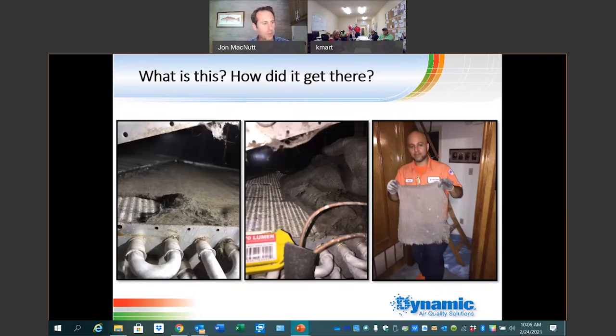But there are quotes where we can talk about the coil and say, not only is that affecting the performance or the efficiency of your system, so now you're overpaying the utility company, but if you're restricting the airflow across the coil, like in this picture here, guys, from a mechanical standpoint, what does that mean to the system when there's going to be higher static pressure in there, choked off airflow? What are some of the mechanical issues we can run into?